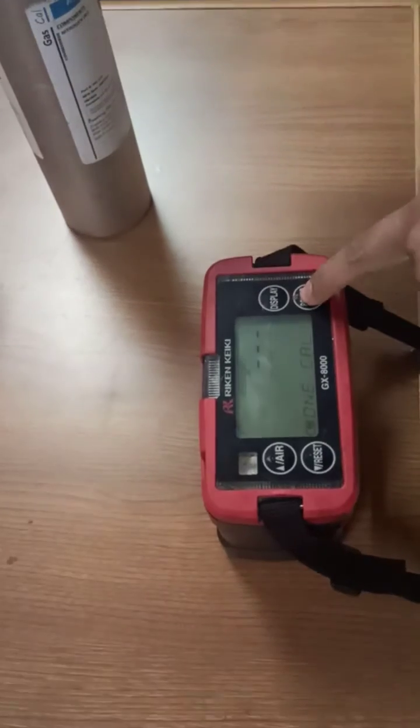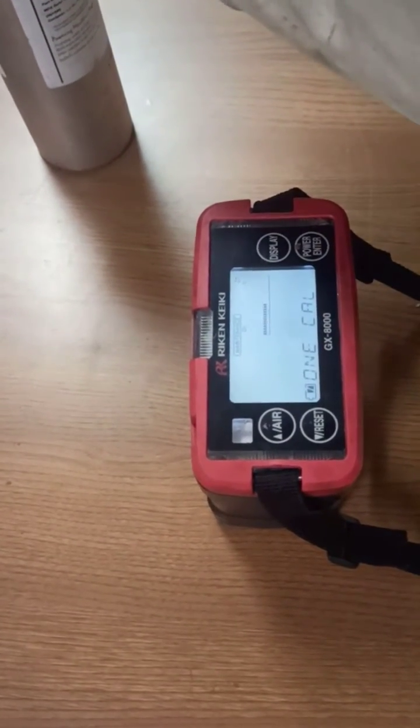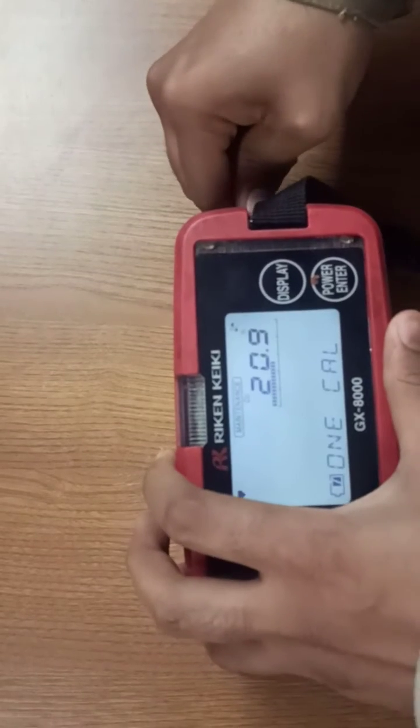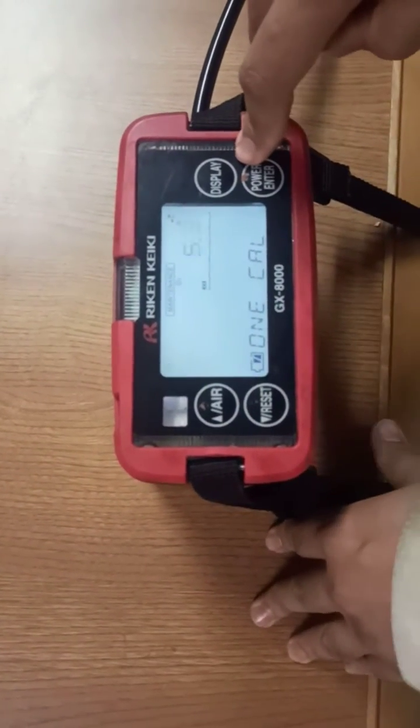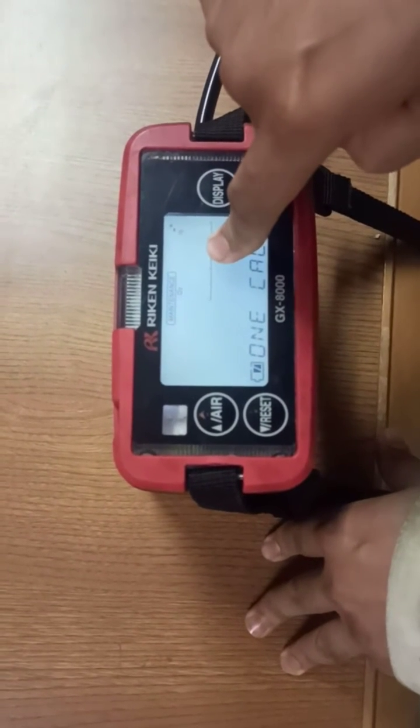Now we will enter the mode. It is showing 20.9 as it should. Now we are connected to the span gas bottle, so it should show nearly zero percentage of oxygen.